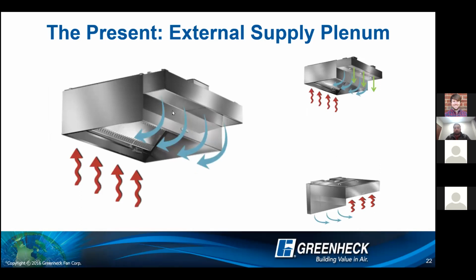So I want to talk a little bit about the plenum itself and the two different kinds that we see used most commonly. The most common plenum in the market is the first one here, which is that ESP plenum. So we have dedicated makeup air coming through this ESP plenum. It's providing an air curtain, so it's providing a slight assist to the capture of that hood. A good portion of that air gets immediately exhausted. The rest of the air goes into the kitchen, and the rooftop units are attempting to dehumidify, to cool, to condition that air.